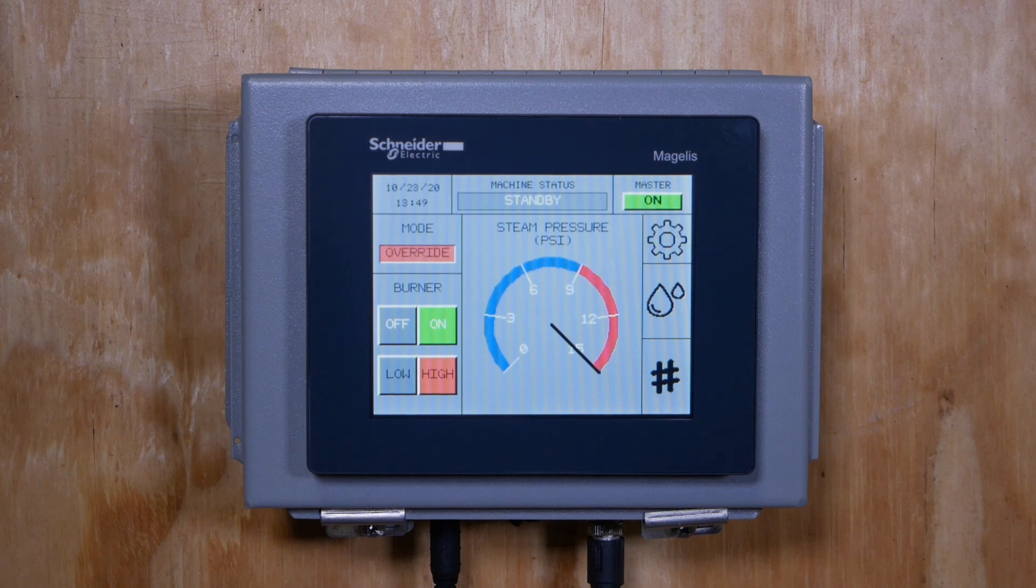Lastly is override mode. This mode is intended for diagnostic purposes only. There is no set pressure available on the touchscreen as it is only controlled by the mechanical limit chain.